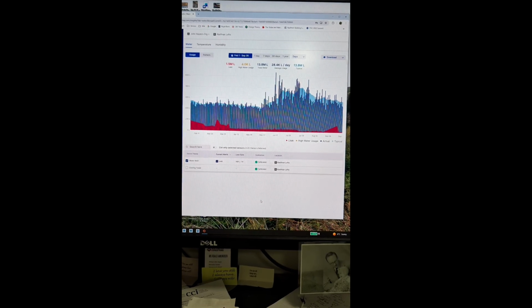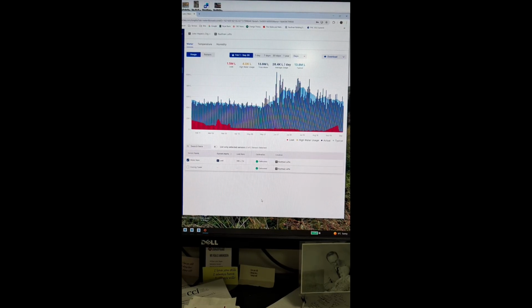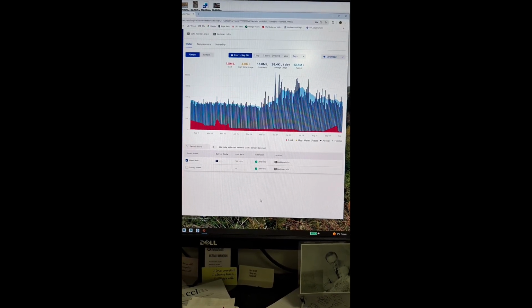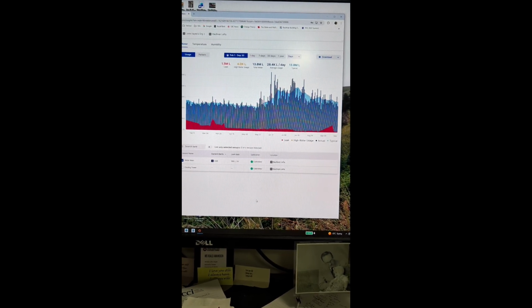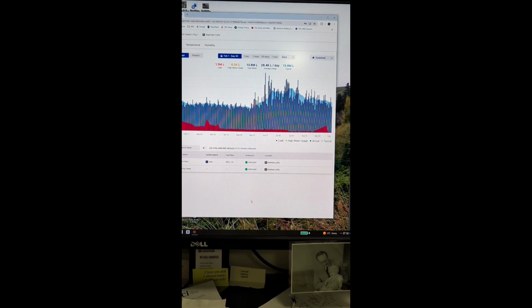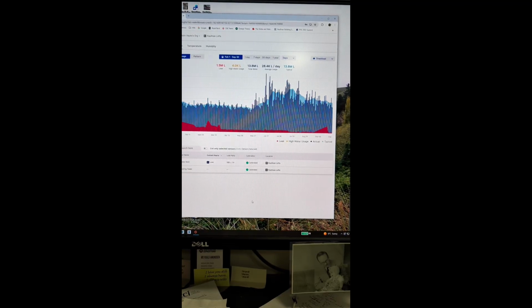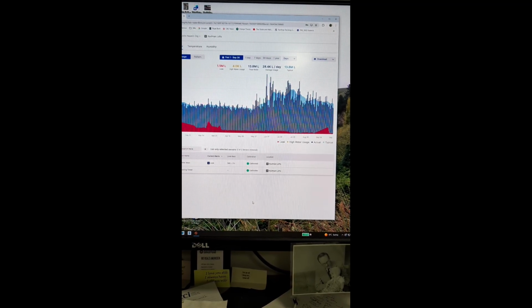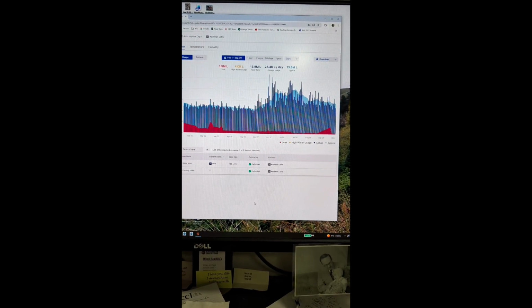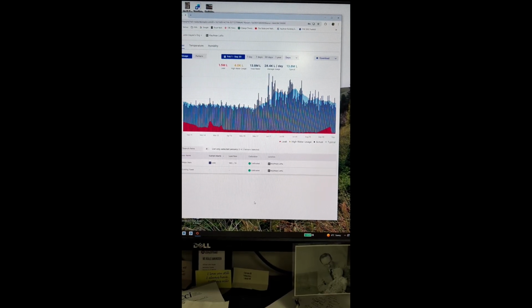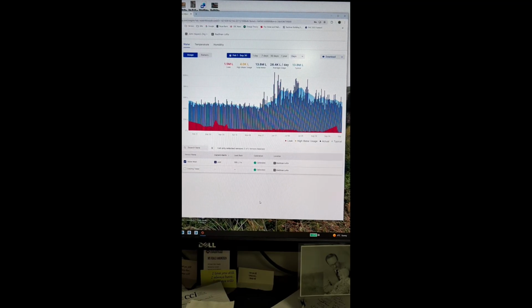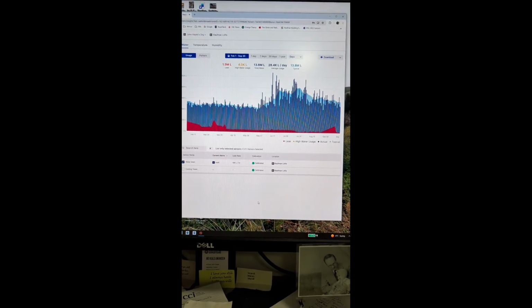And here in my office, we're going to look at the live Alert Labs dashboard on my computer, and I'm going to show you some data from a couple of years ago when we did a leak mitigation program that we can see clearly had an impact. So this chart on the screen shows water consumption over an 8-month period in 2022. The blue bars are daily water consumption, and you can see slightly off to the right, the consumption goes up quite a bit. That's because we have a cooling tower that uses a great deal of water during the summertime, and it peaks up and down based on how hot it is out. Now the red portion at the bottom, that's what the Alert Labs software, which has been monitoring our water consumption through our main water meter by the minute, has figured out is probably water that's being wasted. It's probably going down the drain. And on the left, you can see there's a great deal of water going down the drain.